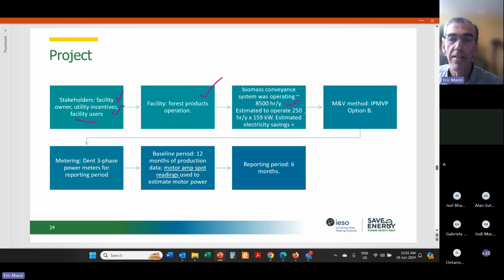And actually the plant staff identified this as an energy saving opportunity because they said, well, it operates 8,500 hours per year. It only needs to operate about 250 hours per year. The plant technical staff estimated that it consumed 159 kilowatts. And so estimated electricity savings were based on that number, which I'll show coming up.